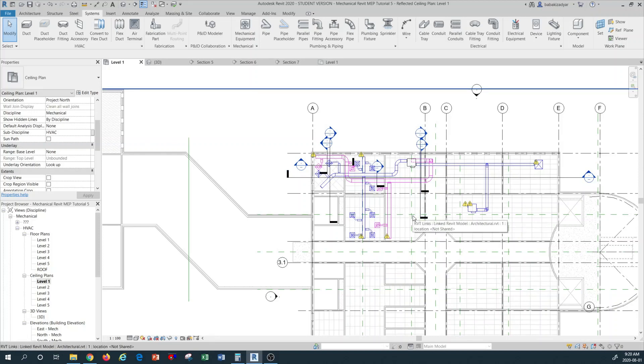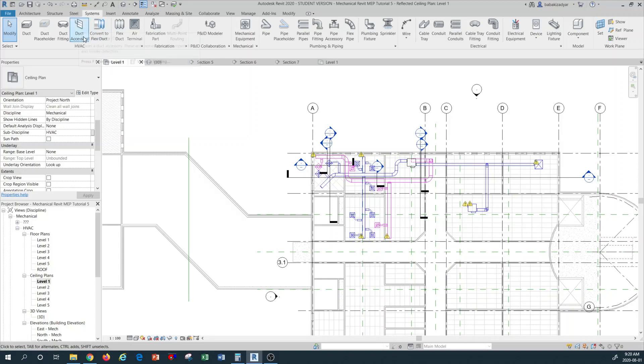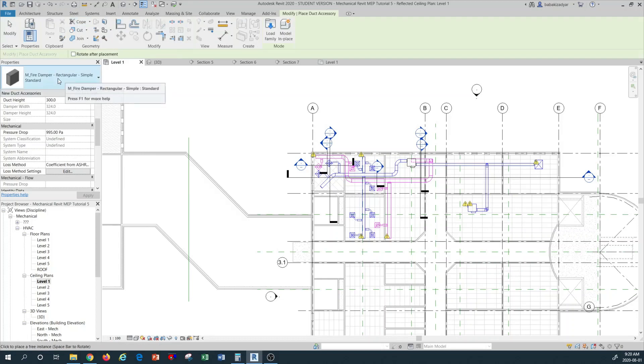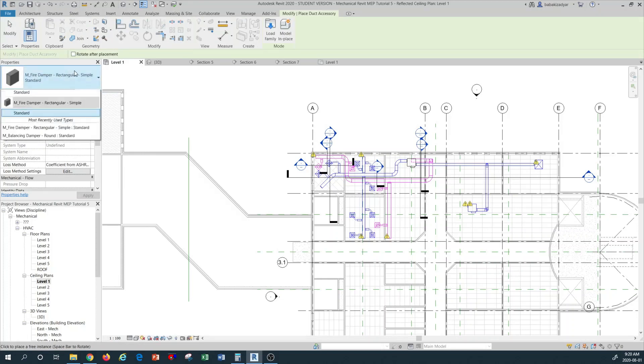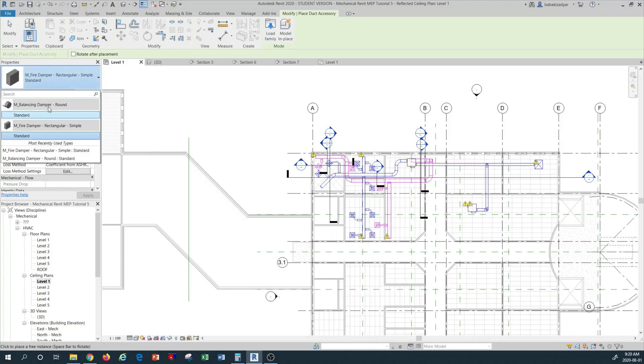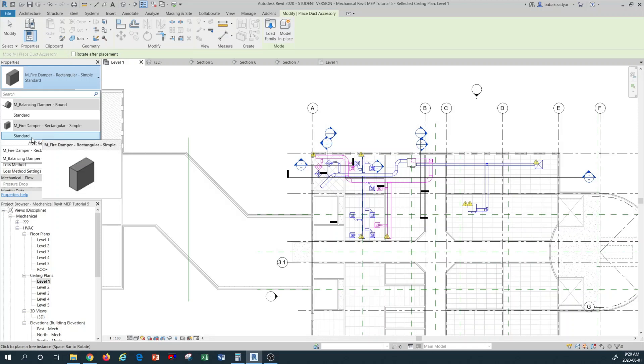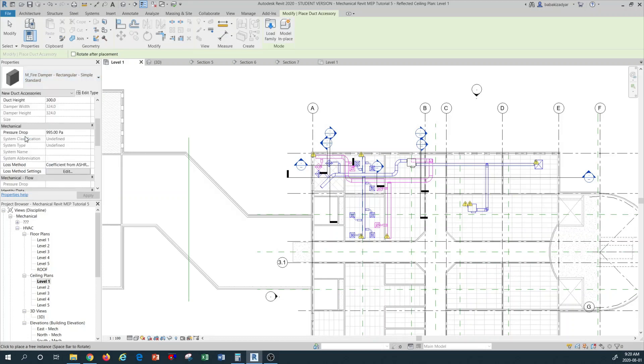To do that, go up to the system tab and find the duct accessory command. By left clicking on that, you come to the directory for the duct accessories. Opening this directory, it looks like we don't have too many options, but for the purpose of this training I would like to add some fire dampers. We're going to go ahead and select the rectangular fire dampers from this directory. I'm going to select the standard — we don't need to change any of the properties of the fire damper. The good thing about Revit is that it is automatically done by recognizing the duct size.